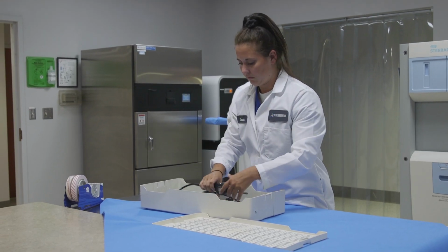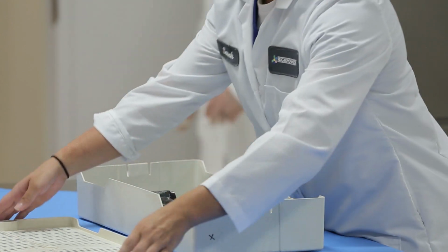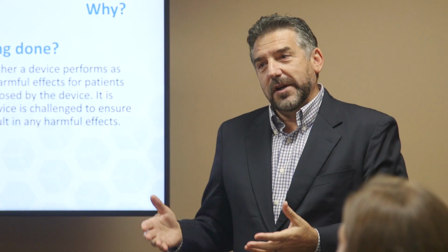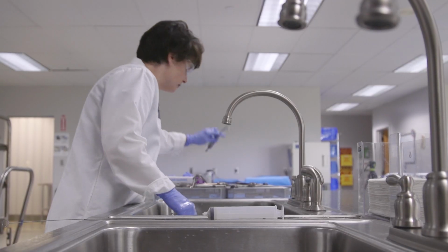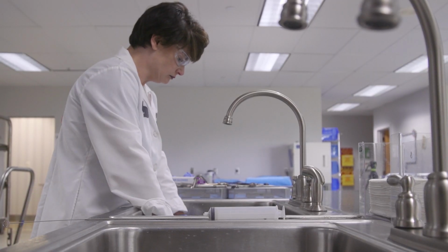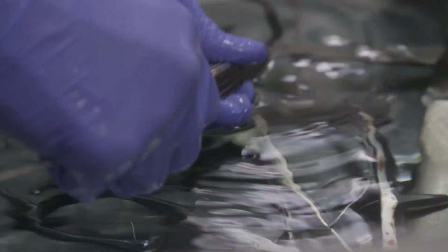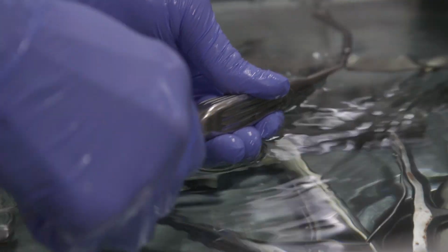Ensuring instructions for use, IFUs, are practical for real-world settings can be challenging. Device manufacturers often rely on the expertise of validation laboratories to aid in developing more realistic reprocessing steps. Validation labs are an insurance policy for the medical device manufacturer. We assist manufacturers during the design and validation phases to develop IFUs that are practical and reproducible. Following a validated IFU produces a safer patient instrument and reduces the chance of shortcuts at the healthcare facility.